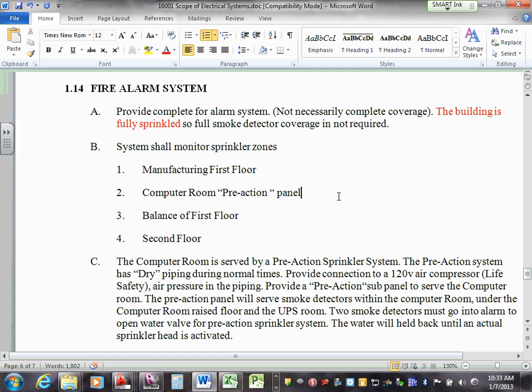If you have a 100% sprinklered building, a lot of the things we used to do with smoke detectors and manual pull stations are no longer required. I believe that's what Matt addresses: what you'd do if you had a fully 100% covered building. That's fine, as long as there's an awareness that you probably won't be doing that in most cases, because owners aren't going to want to pay for 100% smoke detector coverage when they've already paid for a sprinkler system that complies with code and removes the need for full smoke detector coverage. So on a sprinklered building, there may be critical areas: a smoke detector to close a smoke door, a smoke detector to cause the elevator to go to recall, or a smoke detector in a duct on an air handling unit. But other than that, we're not protecting the whole space anymore with smoke detectors.